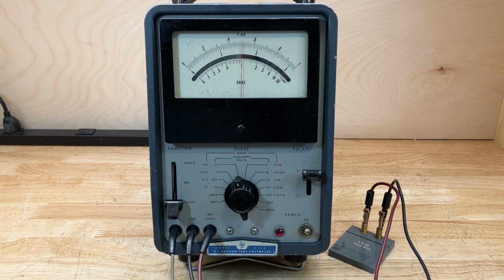Okay, so I spent about an hour cleaning the inside and the outside. It was really quite dirty. I replaced the line cord with a brand new one and realigned everything. It turns out that measurement error we saw was indeed just an adjustment issue. So, put it all back together and we have a completed instrument.